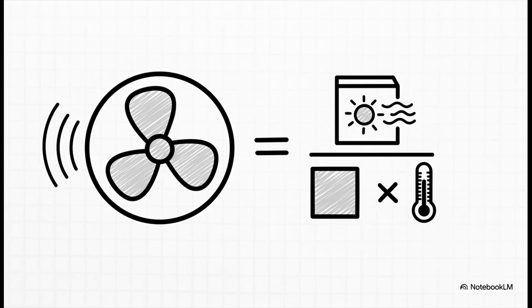But where does that rule of thumb even come from? It's not magic. It's all based on this fundamental formula right here. The required airflow, your CFM, is equal to the sensible heat load, that's the Q, divided by a constant 1.08 times delta T. And delta T is just the temperature difference between the air in the room and the air coming out of the vents. This equation, this is the physics that underpins the entire practice.